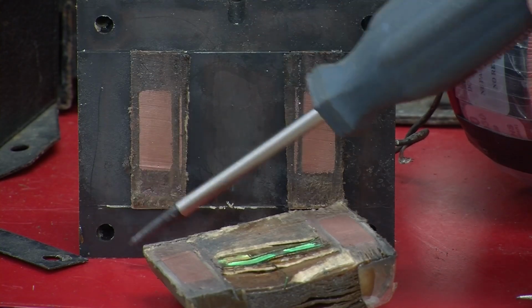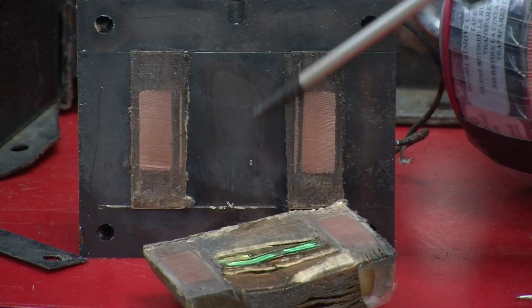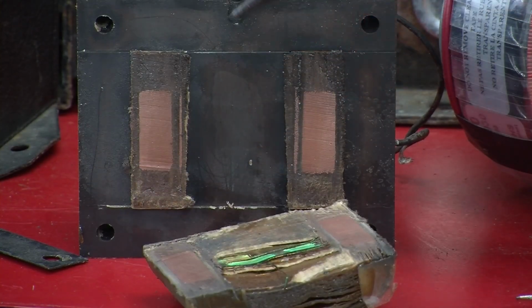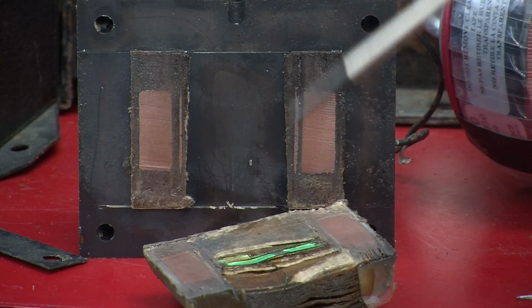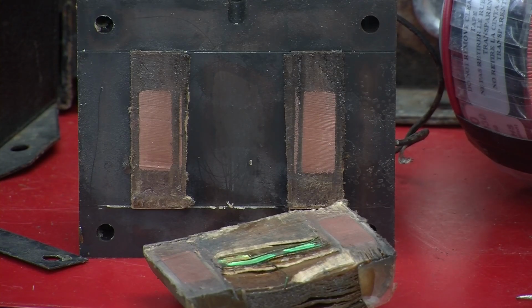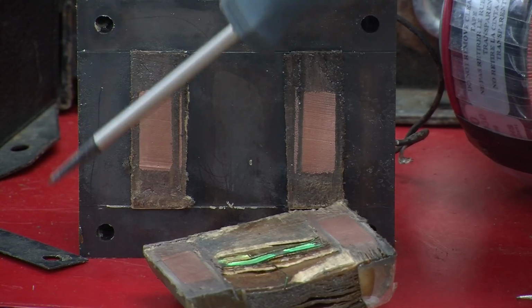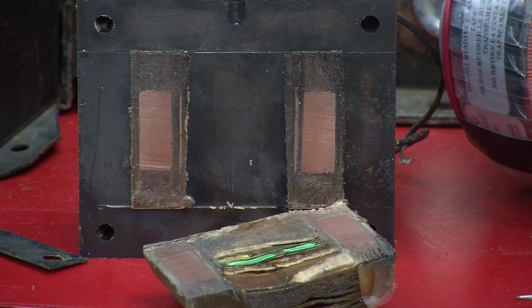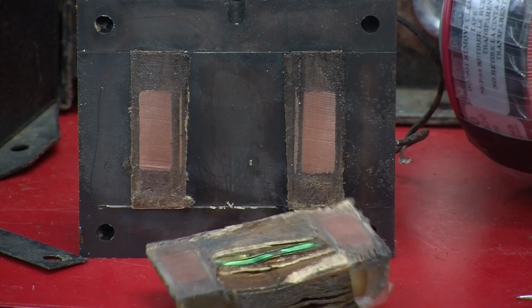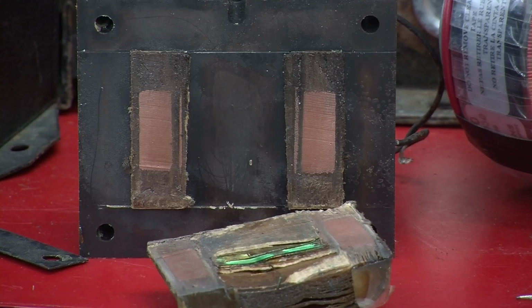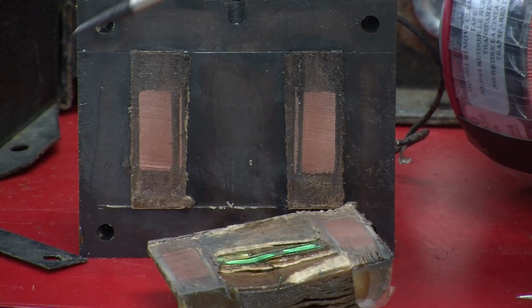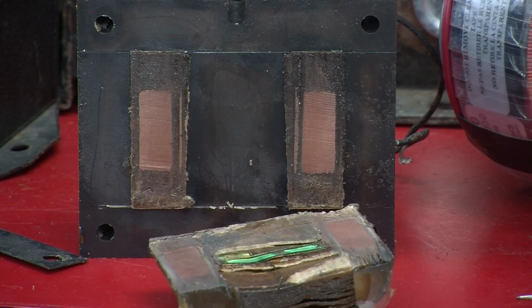In other words, just under around 1 Tesla or so of magnetic flux density. The bigger the core, the more volume of core is subject to those losses, and the greater those losses are. So the bottom line is, you make the core bigger, you have more core losses. Now, the question you might ask is, why would you then make the core bigger?